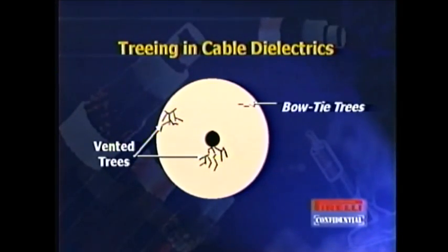And vented trees usually start at the conductor shield or the insulation shield interface and are usually caused by water migrating into the insulation system. That, with the combination of voltage stress, again, will cause a degradation of the insulation, which, as you degrade the insulation over that time, you really have kind of like a hairline crack, and you have a very high stress.